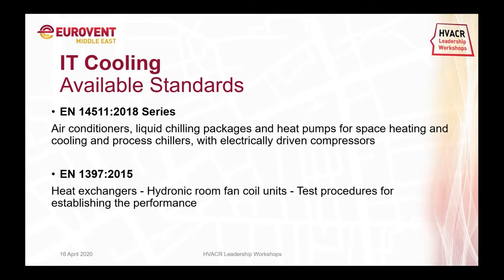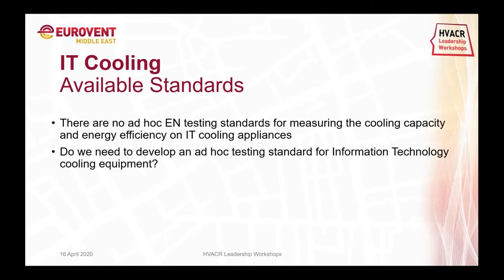Regarding the standards we may apply, we find the EN 14511 series, which deals with air conditioners and heat pumps with electrically driven compressors. This is the standard we could apply when testing CRAC products. We also have the EN 1397 standard, which deals with hydronic fan coils and implements the same method we can use for the performance evaluation of the CRAH unit. In Europe, we do not have any specific standards dedicated to IT cooling technologies, so for the moment we rely on ASHRAE standards or the standards previously introduced.